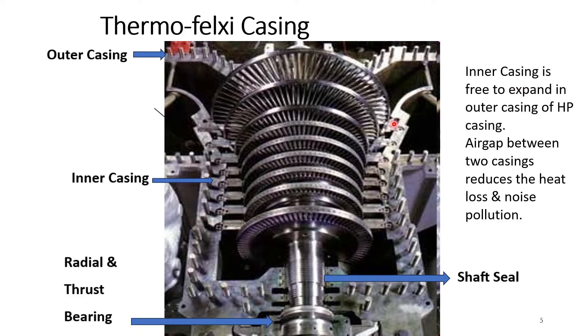The turbine casing is a flexi thermo casing — we call it a thermo flexi casing. There are two casings in the turbine: the outer casing and the inner casing. We call them flexi casing because the inner turbine casing can slightly expand when it is heated and contract when it is cooled. An air gap is provided between the two casings to reduce heat loss as well as to reduce noise pollution.